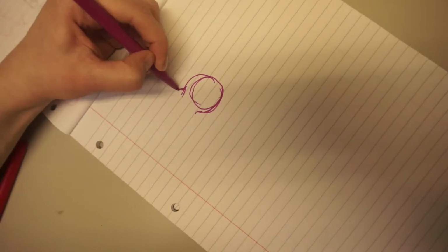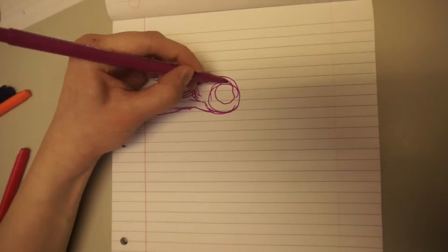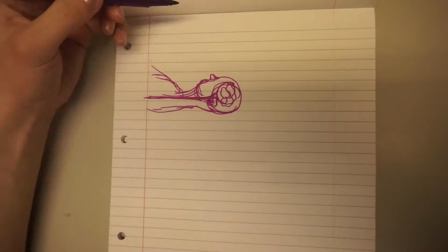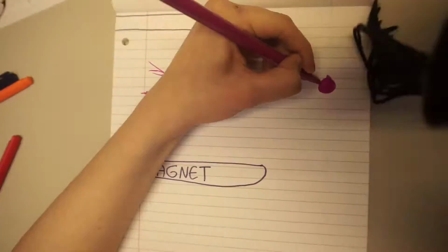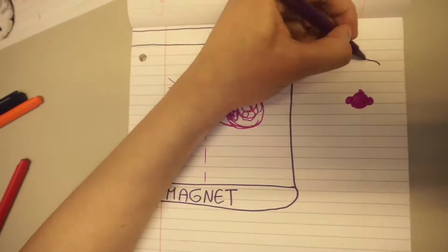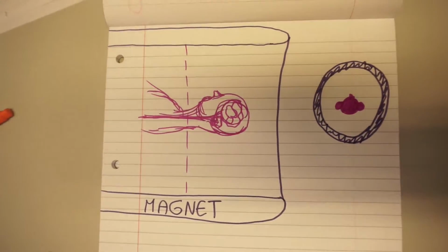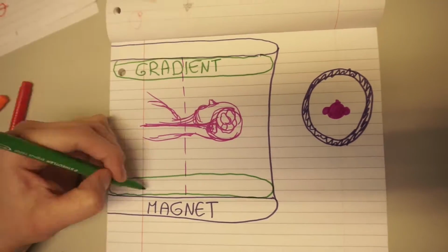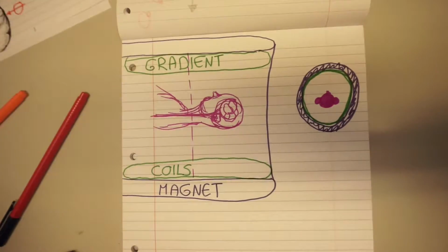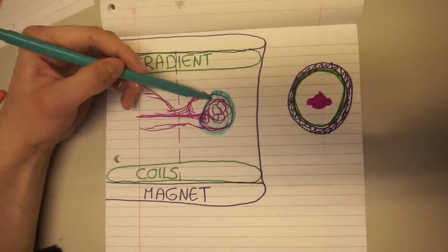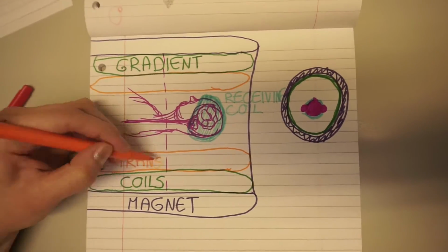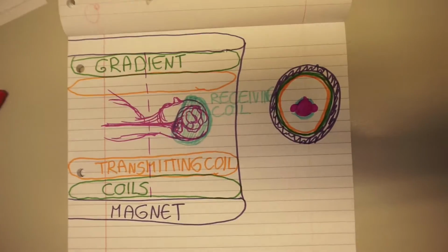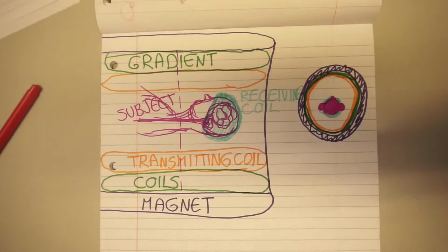Now this is where it gets interesting, when we place someone or something into a large bore magnet in an MRI scanner. A clinical scanner has 3 major components: a bore magnet coil to supply the external and strong magnetic field, gradient coils to provide additional and modulating magnetic fields, and transmitting and receiving RF coils to excite the protons and measure the signal from their relaxation.